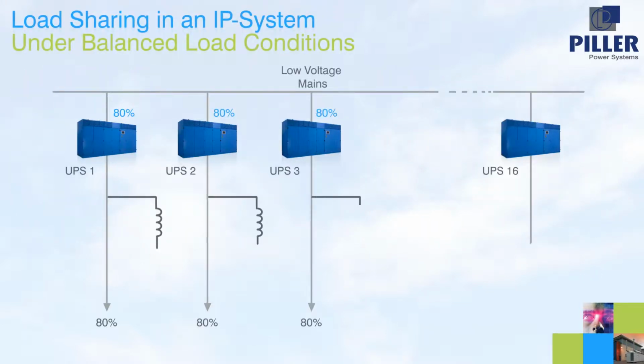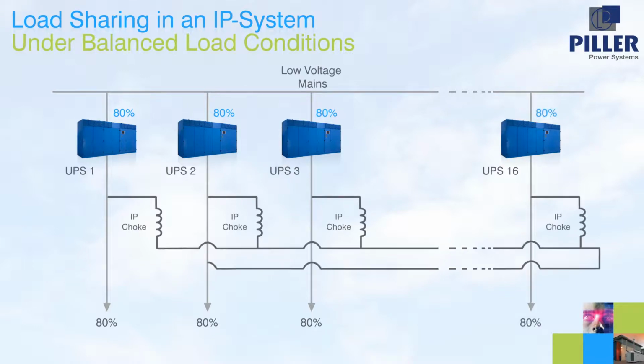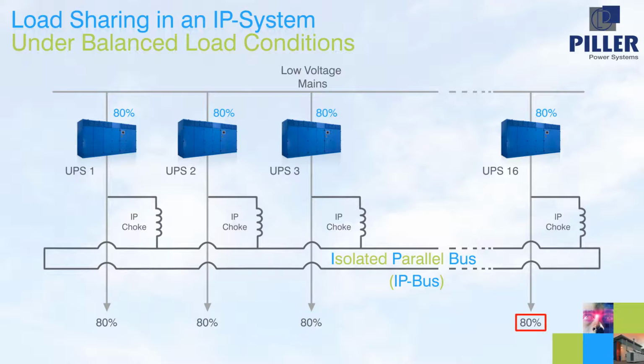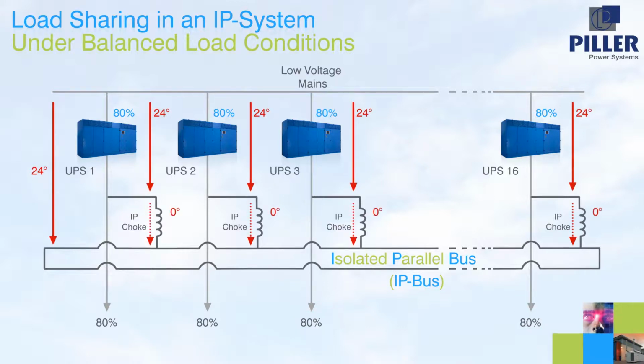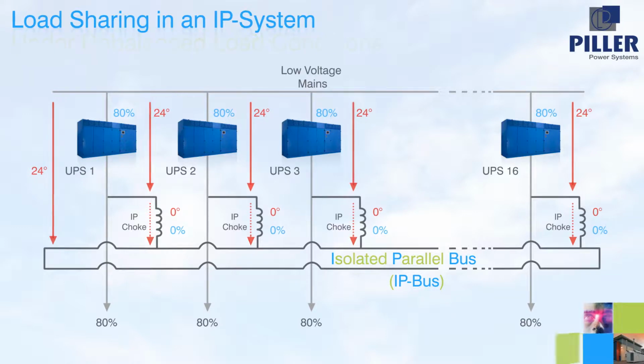We'll now use a 16-module system to demonstrate both the responses and the enormous flexibility of this design under various steady-state and dynamic conditions. Under equal load conditions, for example 80% load on each UPS, we see the same phase angle across every unit, resulting in zero phase angle across the IP chokes. With no phase angle across the IP chokes, there is no power flowing through the chokes and hence around the IP bus, resulting in every UPS carrying its own load completely.